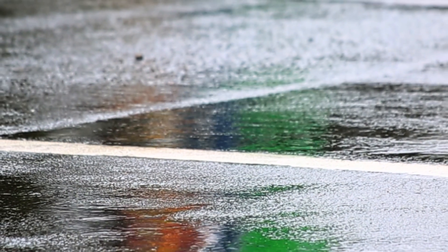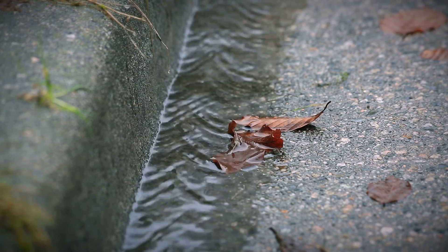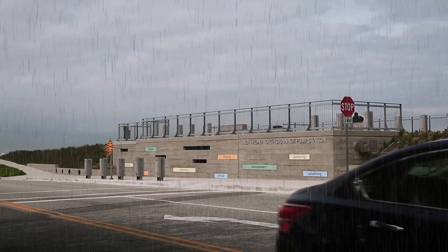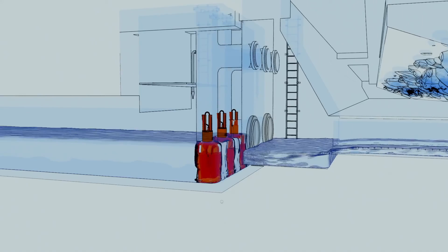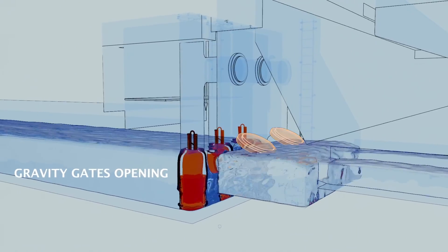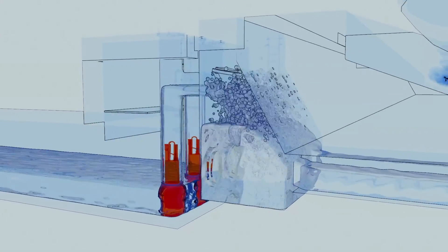Here's how it works. When it rains, water falls onto our rooftops, driveways, and roads. From here, rainwater enters the drainage system through catch basins, where it's conveyed to the City's outfalls and pump stations. At low tide, the water flows to the pump station with no assistance from the pump. At high tide, underground sensors detect the water levels rising and automatically start the pumps, which continue to operate until the water levels drop.